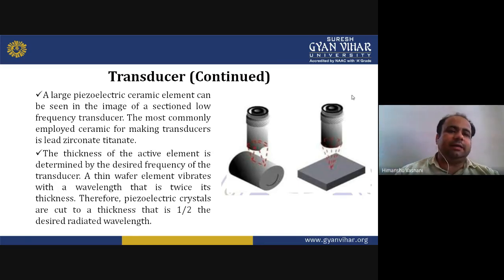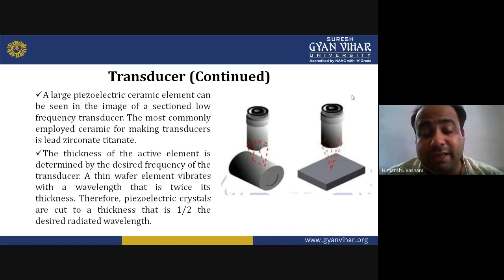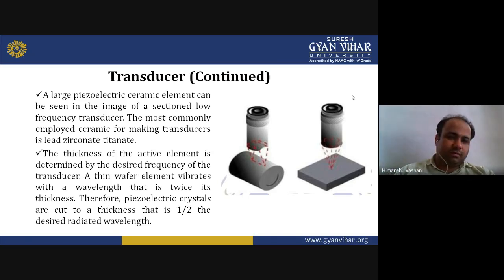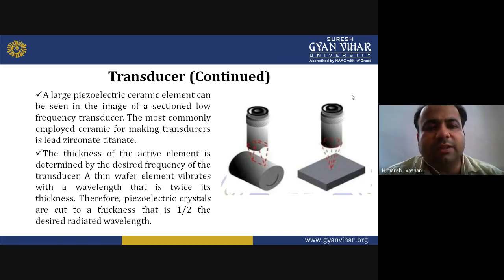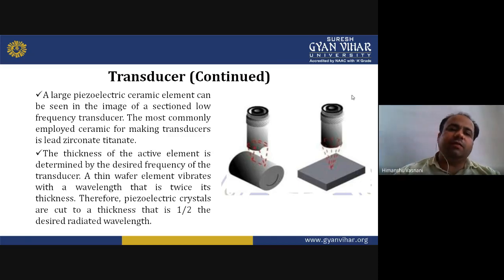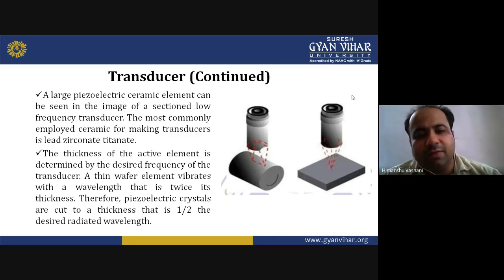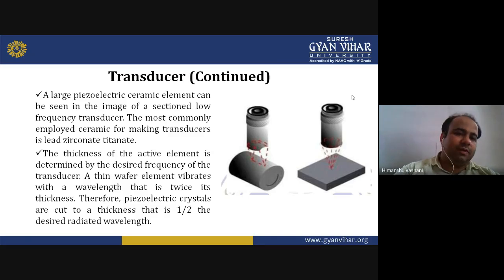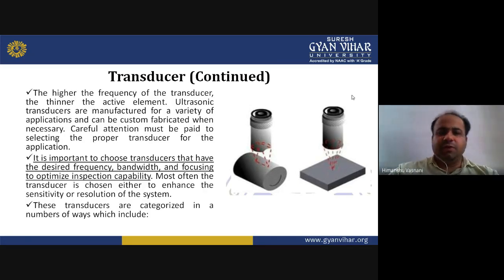The most commonly employed ceramic for making transducers is lead zirconate titanate. This is the most commonly used ceramic for making the transducer. Now, the thickness of an active element is determined by the desired frequency of the transducer. A thin wafer element vibrates with a wavelength that is twice its thickness. Therefore, a piezoelectric crystal is cut to a thickness that is half of the desired radiated wavelength. The higher the frequency of the transducer, the thinner the active element.